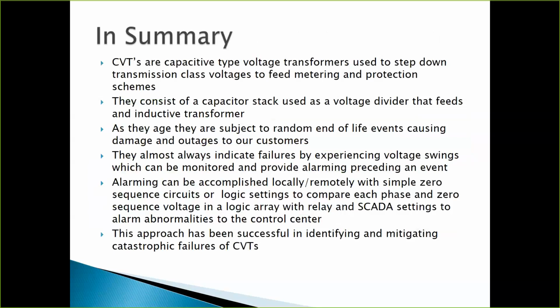All right, in summary, CVTs, they are capacitive voltage type transformers. They're used to step down a transmission class voltage, typically 100 kV, 230 kV, even 525 kV. We use them for metering applications, for protection applications, for control applications. They supervise reclosing, they initiate swap overs. So they're a very useful device. They're a very inexpensive way to step down transmission class voltages, to use them for these applications.